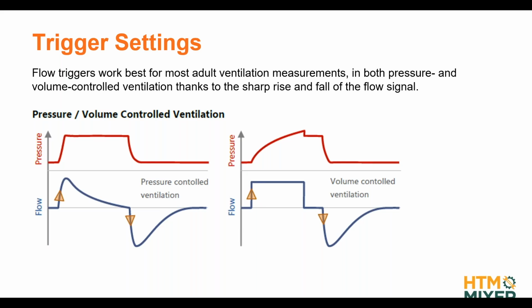And because of that, all gas flow analyzers out there have default trigger settings which are exactly based on that. Okay, that's the good news. So they work in, let's say, 95% of your applications, as long as you have a positive and negative flow through your gas flow analyzer. Some analyzers have different presets for adult, pediatric, and high frequency. But in most applications, you just switch it on and see, oh yeah, it's triggering, and most likely it's going to work.